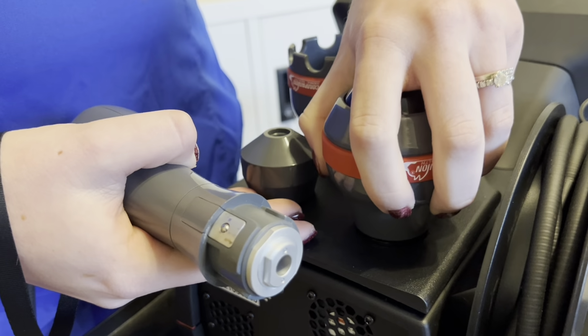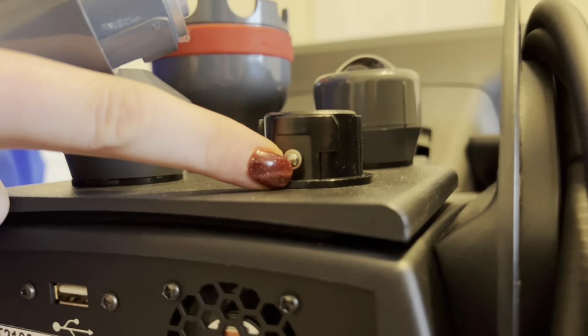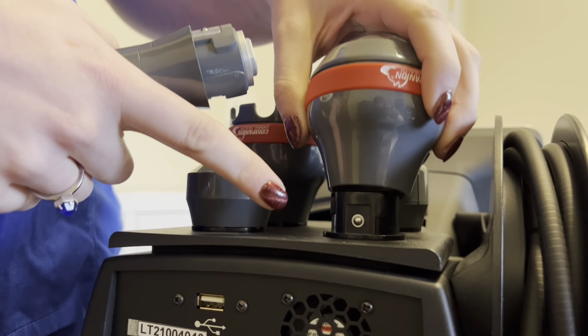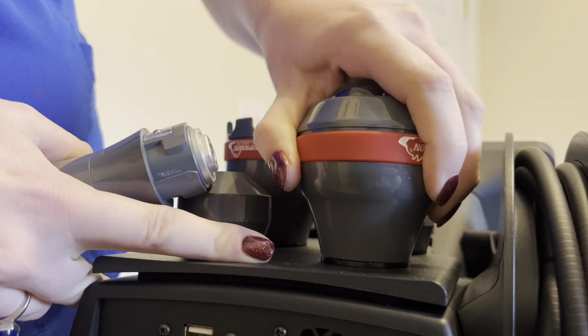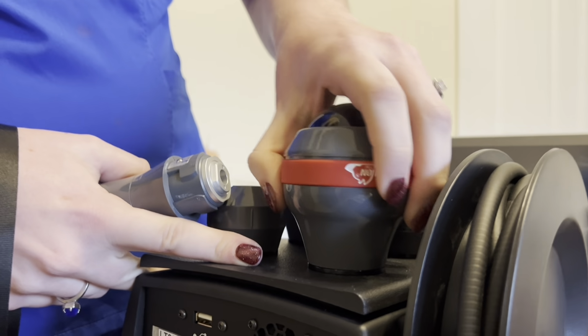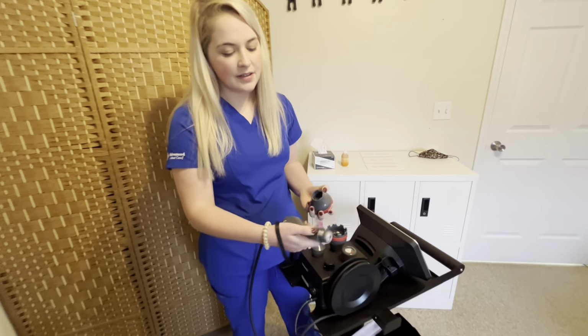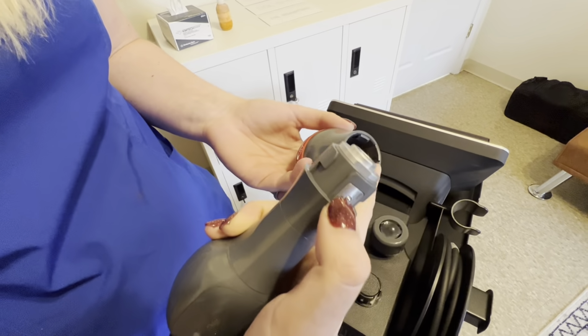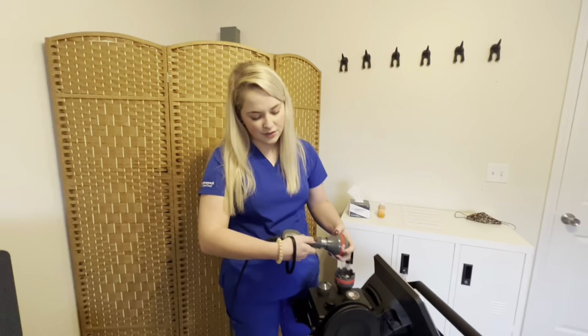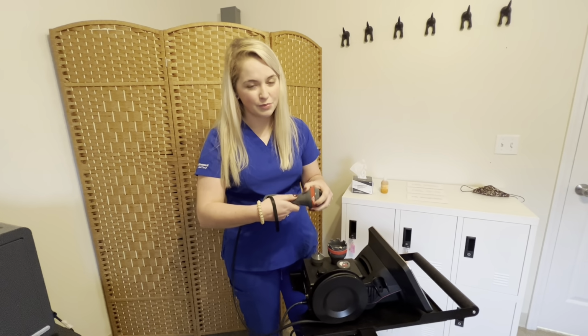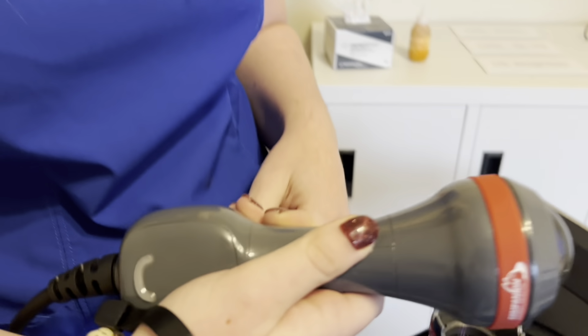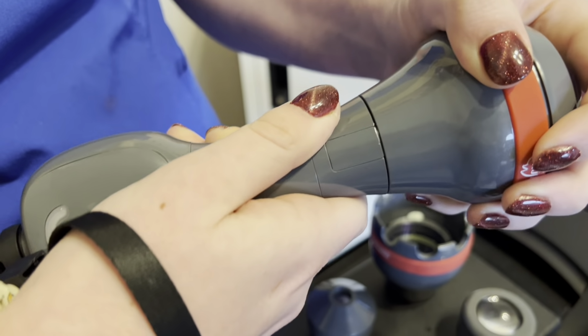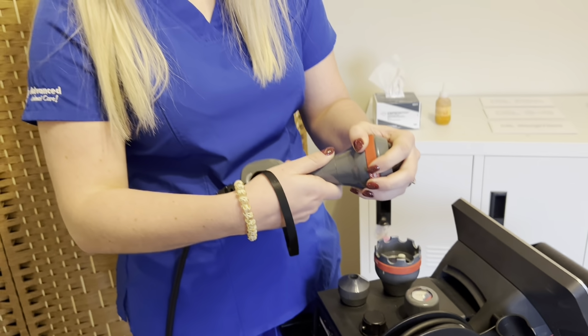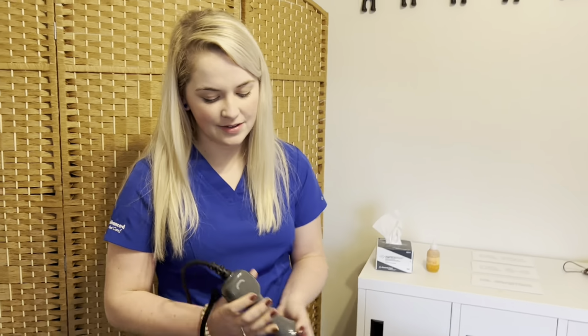If you get on here, you turn it, and it comes off. There is a middle portion right here with this little ball. It communicates with this other middle portion within the treatment head. So when you're going back to put it on, you slide it down and turn it. You hear that click. That's when you know it is locked. If you just push it down, it's still roaming. So you have to make sure when you push it down, you hear that click and it's locked in. Same goes for the handpiece. On the handpiece, you have a metal ball here that communicates with the middle tab within the treatment head. You make sure those line up. You push it on. This is not locked yet, so you push it on and you turn it. You hear the click, and now it's locked onto the handpiece. When you go to take it off, turn it and pull it off. Turning it on, click, turn it, and make sure it's locked onto the handpiece. That way, now you're ready to do your treatment.